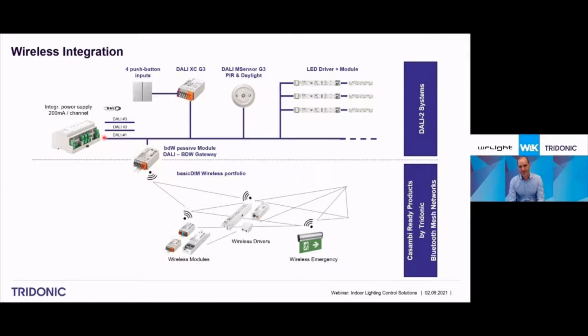It's really a great feature that up to 64 Bluetooth devices, maximum per DALI line, can be used on the sceneCOM Evo system, because the DALI gateway translates each Bluetooth device to a DALI short address. So for the sceneCOM Evo, the Bluetooth devices look like standard DALI devices and can be handled, processed, commissioned and used just like a standard DALI device connected via wires. This gateway enables the translation from Bluetooth to DALI 2, which brings a lot of benefit. We're now also working on getting wireless sensors and wireless user interfaces translated.